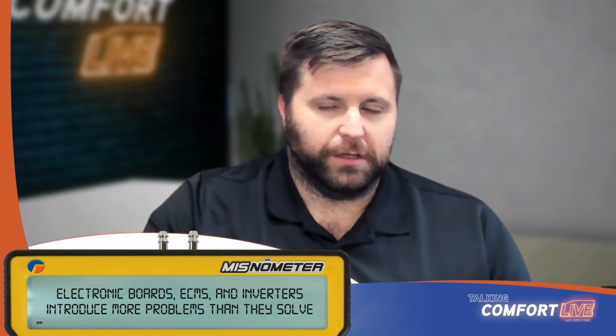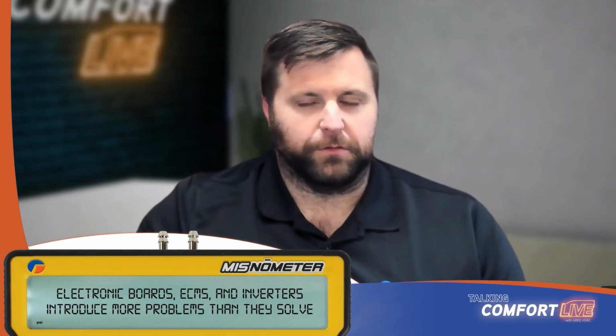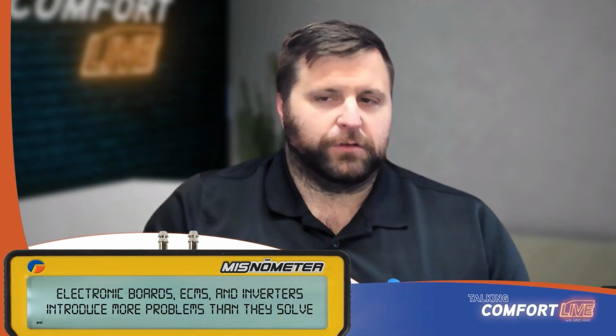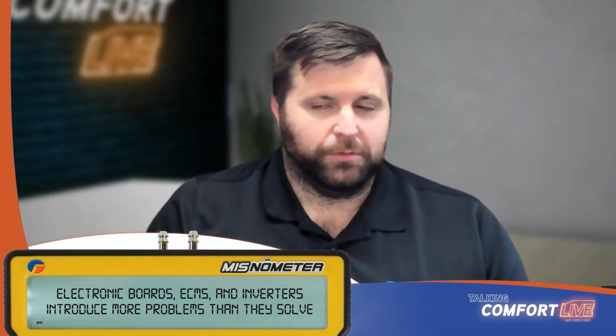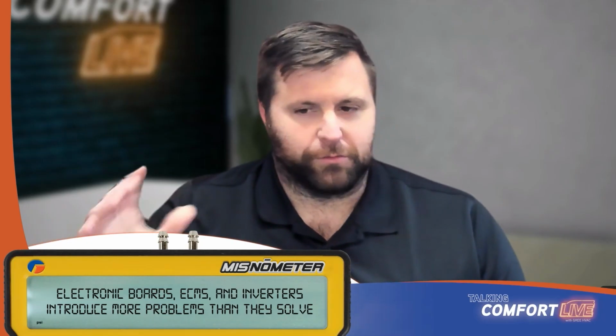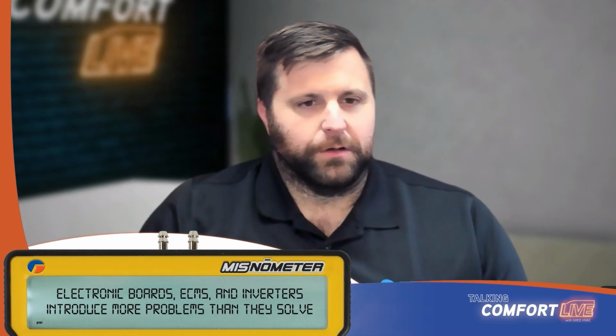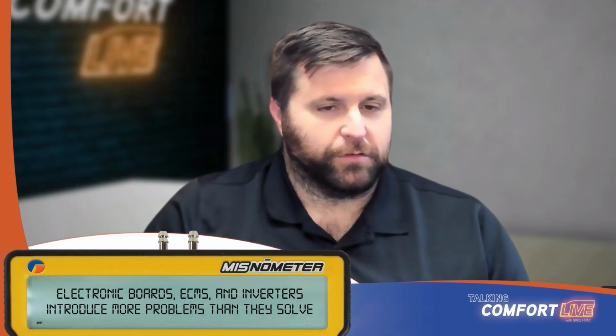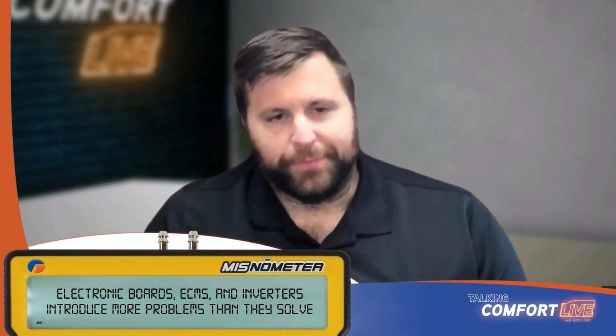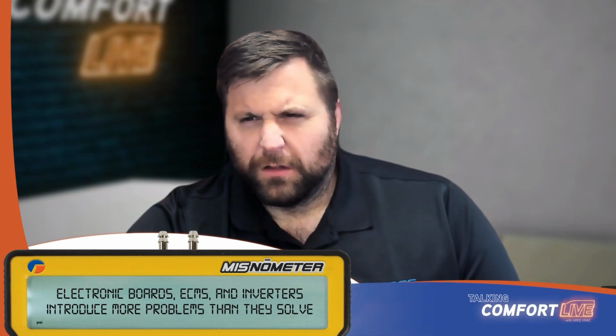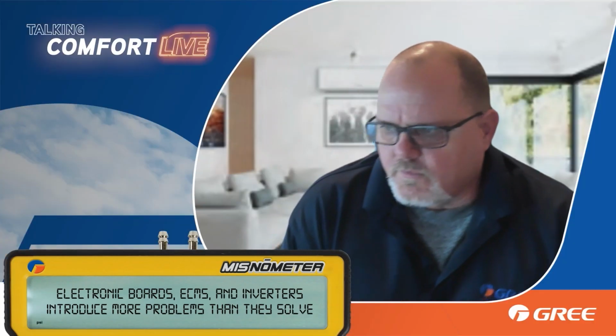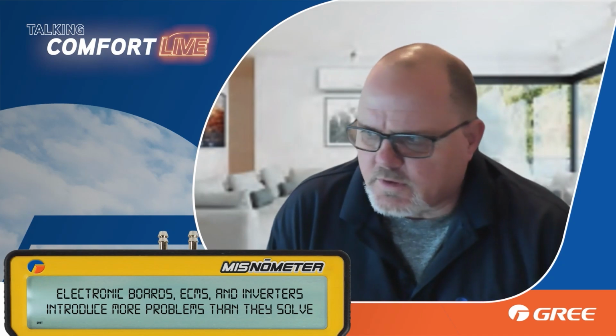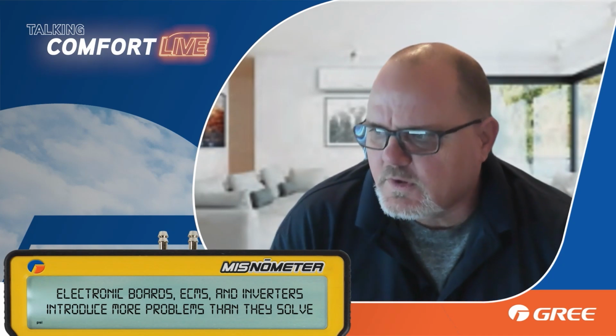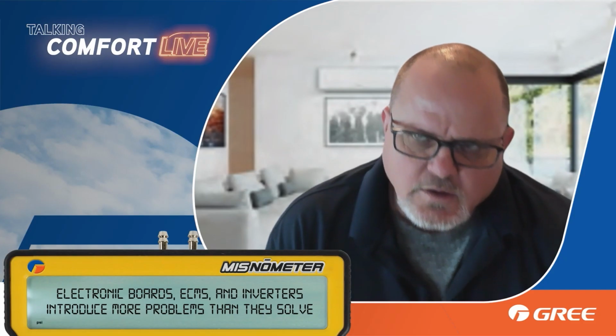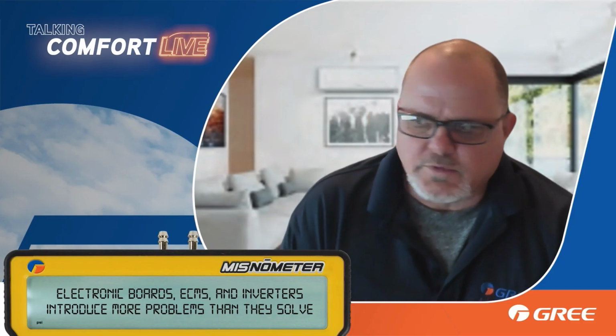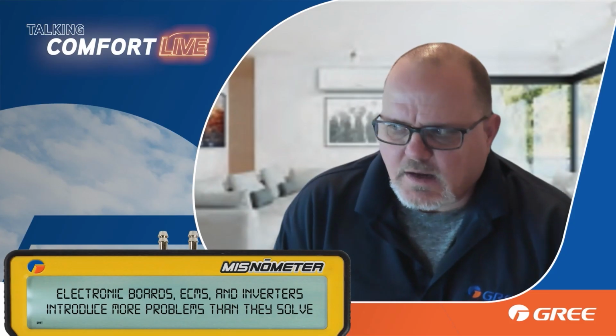One of the great things that we did, like with the Flex or with our Multi-Pro systems, is that we're able to get efficiencies out of them that you can't get by just making a bigger coil or a more efficient fan motor. We can get efficiencies by slowing down the compressor, that kind of thing. So let's circle back here to the misnomer. The misnomer is that electronic boards, ECMs, and inverters introduce more problems than they solve, which I think we're on board when we say here that I don't think so.